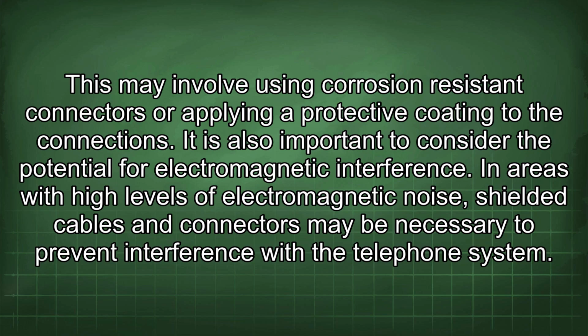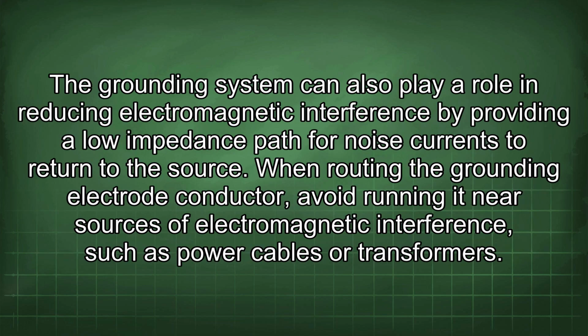It is also important to consider the potential for electromagnetic interference. In areas with high levels of electromagnetic noise, shielded cables and connectors may be necessary to prevent interference with the telephone system. The grounding system can also play a role in reducing electromagnetic interference by providing a low impedance path for noise currents to return to the source.